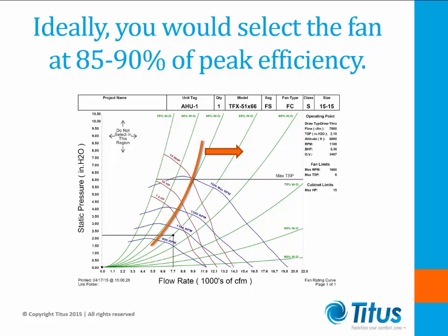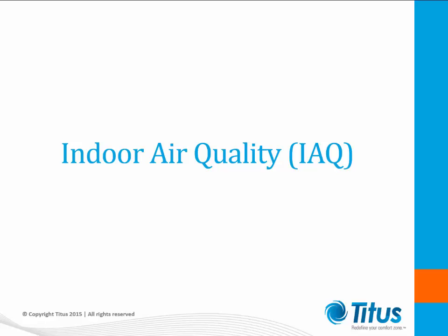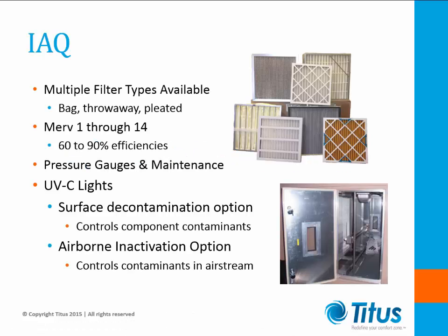it is also important to not select the fan operating points too far to the right of the peak static efficiency. When done so, the fans are less efficient in operation and may also have more noise issues in the field. Our next topic of discussion will be the indoor air quality.